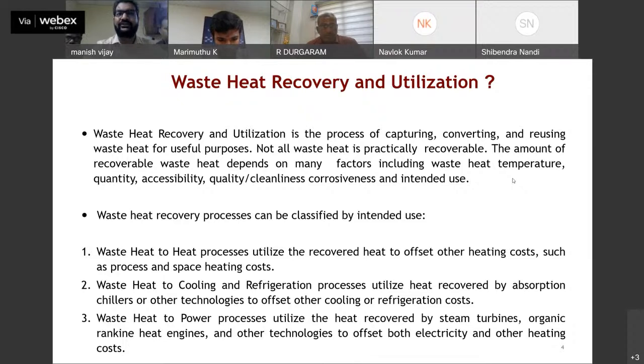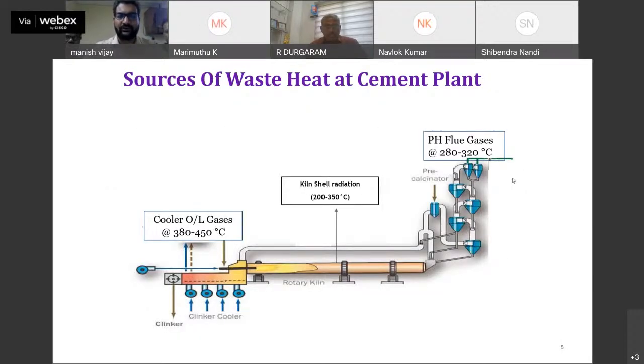The waste heat generated from any process can be converted in three ways. First, to use for drying of any material. Second, for the refrigeration process by using the vapor absorption and vapor adsorption cycles. Third is to generate power by the organic Rankine cycle or the normal Rankine cycle. As I have already told you, in a cement plant there are basically three heat sources: cooler outlet, kiln shell, and the PH flue gases.